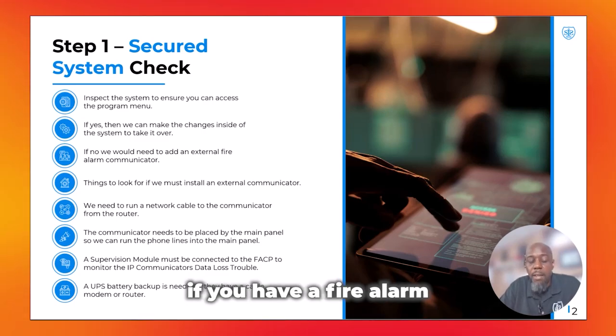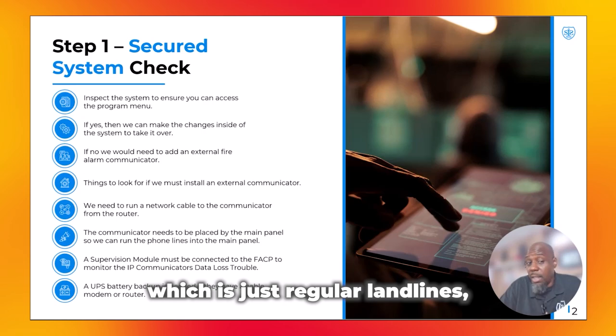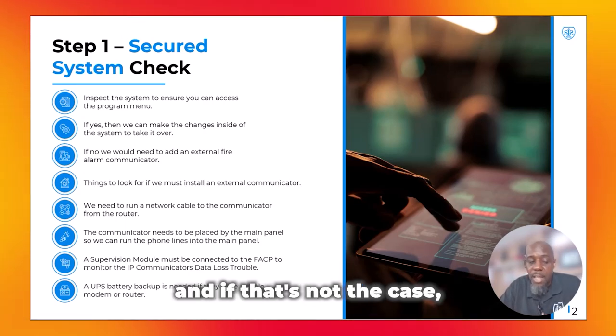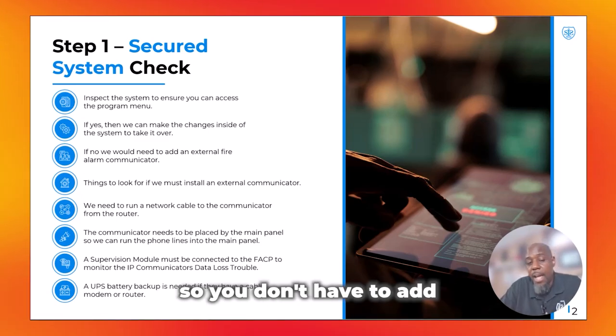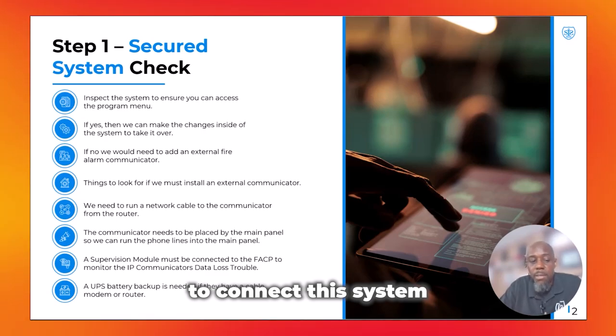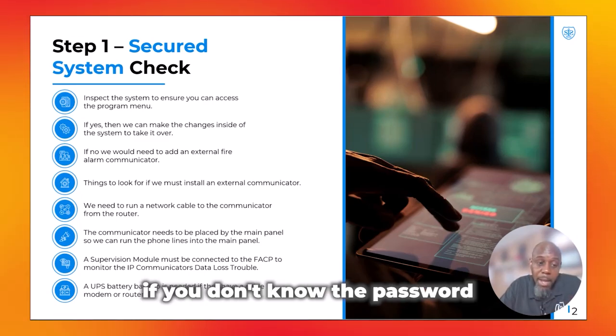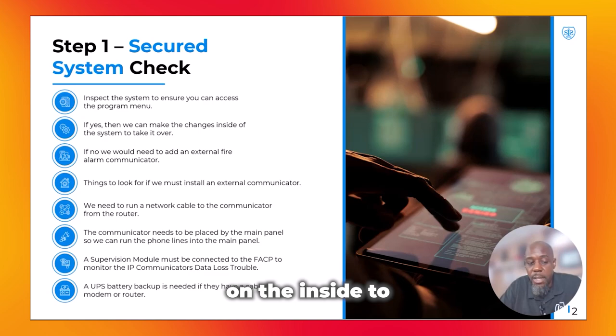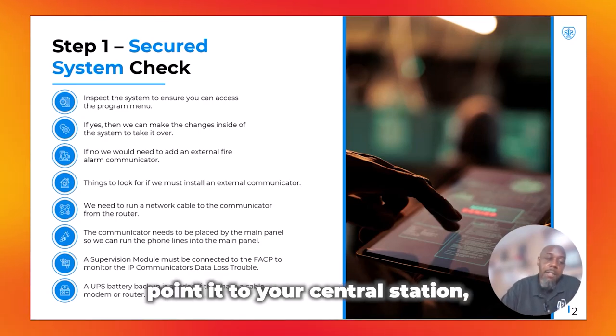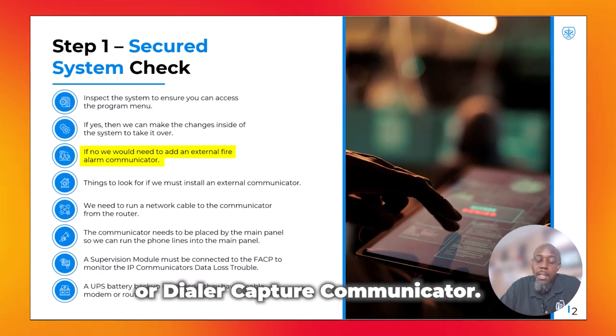This is usually the case if you have a fire alarm system connected on a POTS line, which is just a regular landline. If you can get into the menu, make those program adjustments and you don't have to add any additional equipment to connect the system to your central station. But if you can't get the password and can't get into the menu to change the information and point it to your central station, then you would have to use an IP dialer or dialer capture communicator.